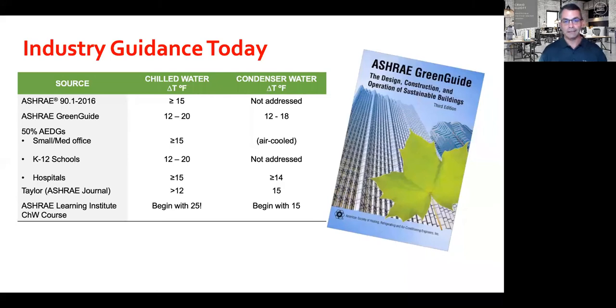ASHRAE industry guidance has changed over the years. Many of us may still use a rule of thumb of 10-degree delta T with a 45 or 42-degree leaving water temperature, depending on your climate. Today, we see the more efficient plants operating at a higher delta T.